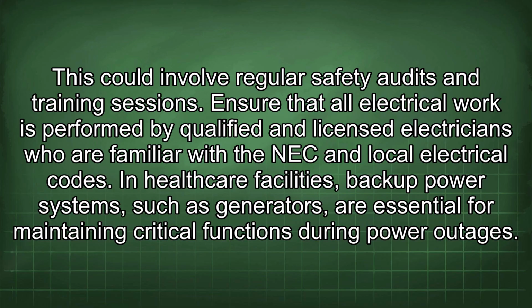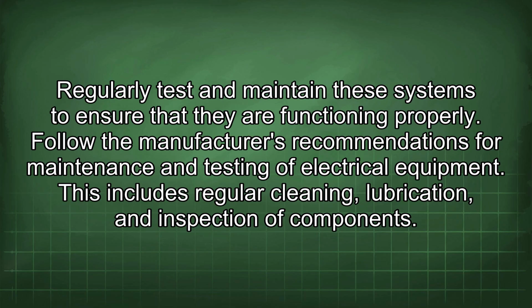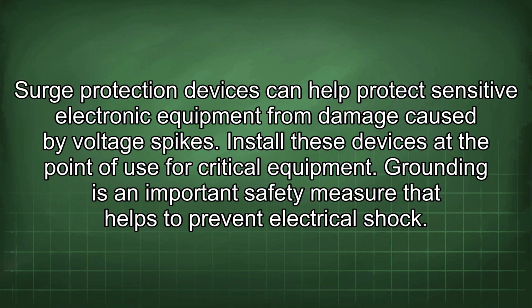electrical codes. In healthcare facilities, backup power systems, such as generators, are essential for maintaining critical functions during power outages. Regularly test and maintain these systems to ensure that they are functioning properly. Follow the manufacturer's recommendations for maintenance and testing of electrical equipment. This includes regular cleaning, lubrication, and inspection of components. Surge protection devices can help protect sensitive electronic equipment from damage caused by voltage spikes. Install these devices at the point of use for critical equipment.